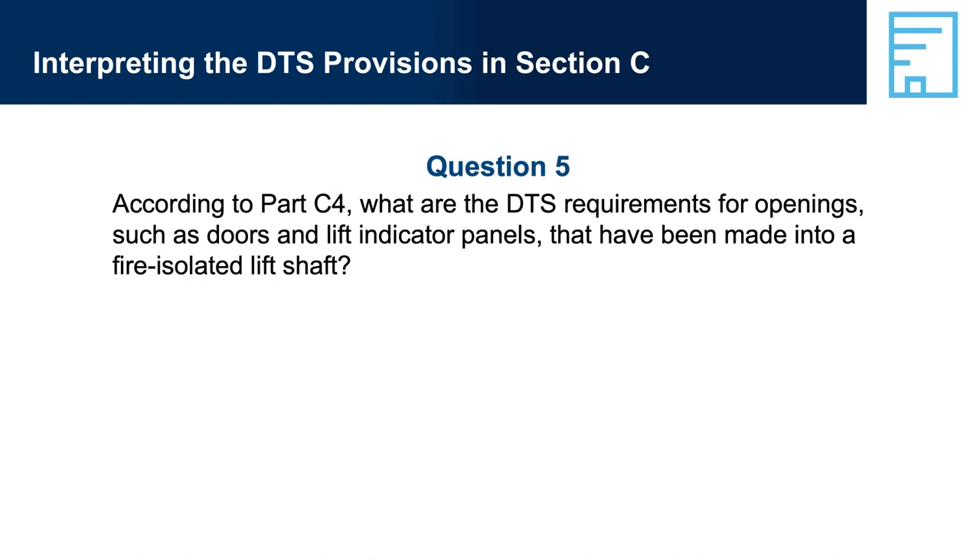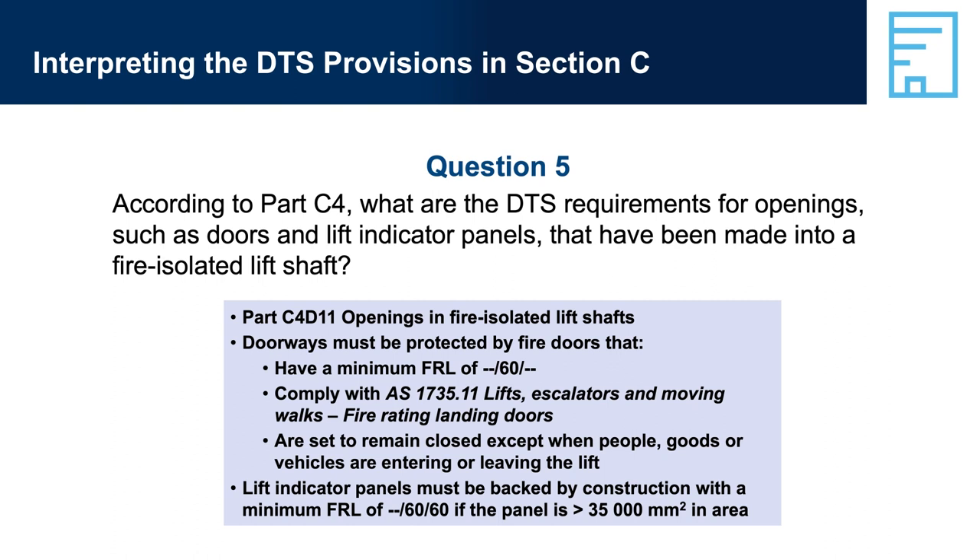Question 5: According to Part C4, what are the DTS requirements for openings such as doors and lift indicator panels that have been made into a fire-isolated lift shaft? Answer 5: Part C4-D11, Openings in Fire-Isolated Lift Shafts — doorways must be protected by fire doors that have a minimum FRL of -/60/-- and comply with AS 1735.11, and are set to remain closed except when people, goods, or vehicles are entering or leaving the lift. Lift indicator panels must be backed by construction with a minimum FRL of --/60/60 if the panel is more than 35,000 square millimetres in area.